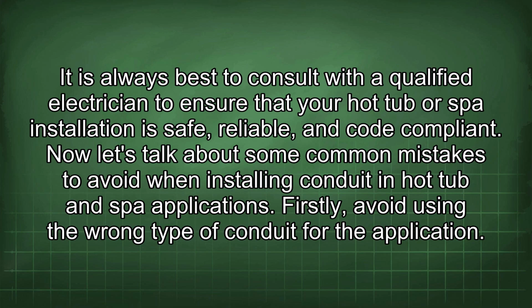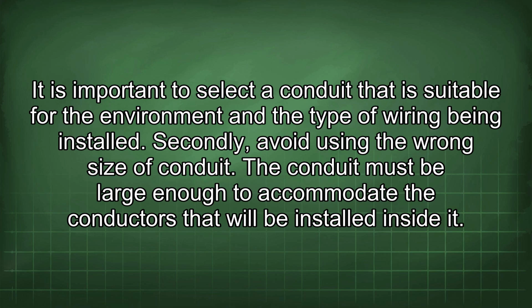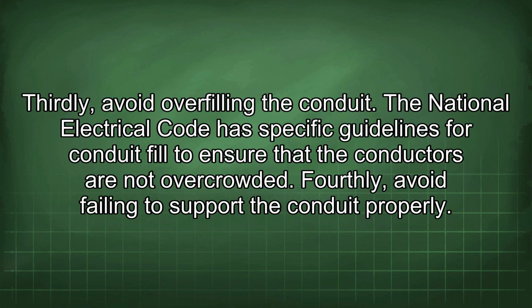Now let's talk about some common mistakes to avoid when installing conduit in hot tub and spa applications. Firstly, avoid using the wrong type of conduit for the application. It is important to select a conduit that is suitable for the environment and the type of wiring being installed. Secondly, avoid using the wrong size of conduit. The conduit must be large enough to accommodate the conductors that will be installed inside it. Thirdly, avoid overfilling the conduit. The National Electrical Code has specific guidelines for conduit fill to ensure that the conductors are not overcrowded.